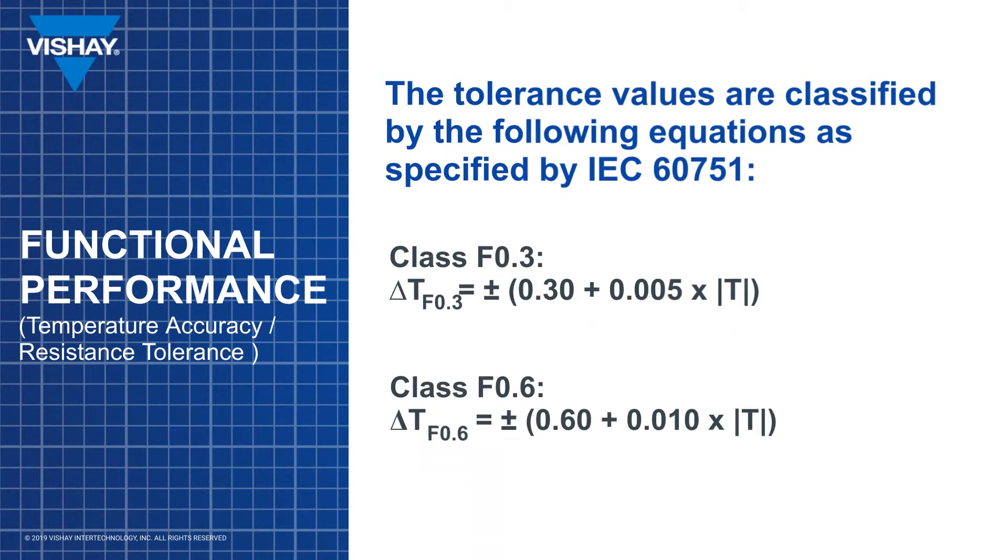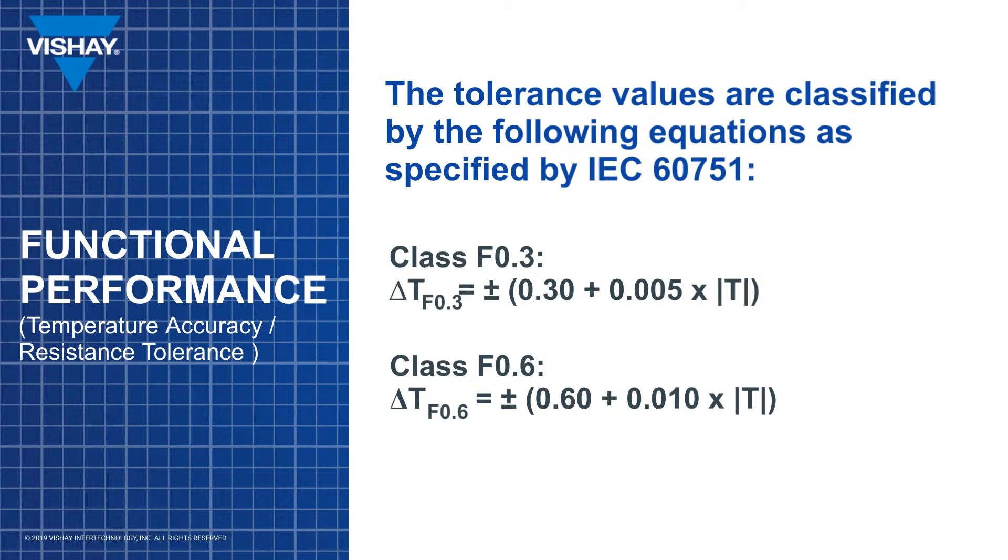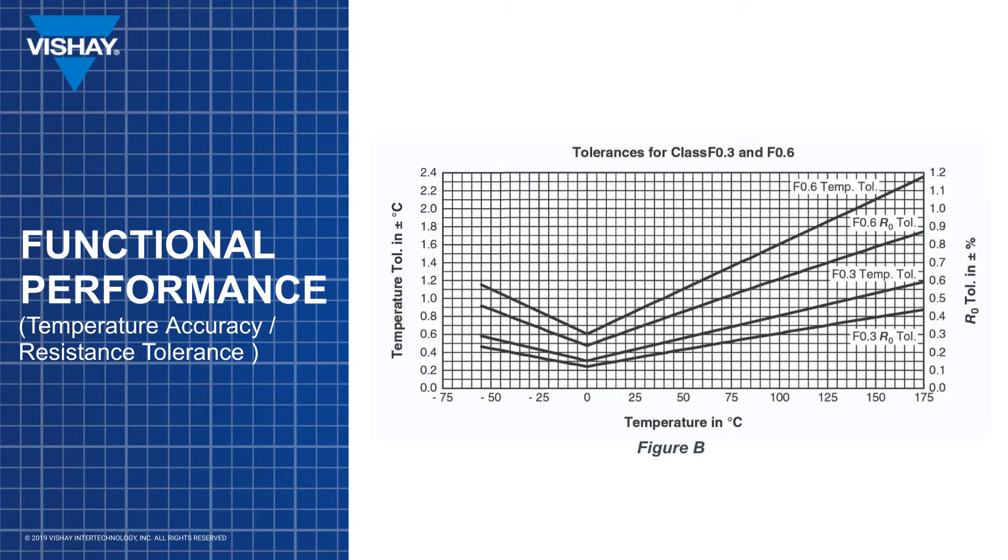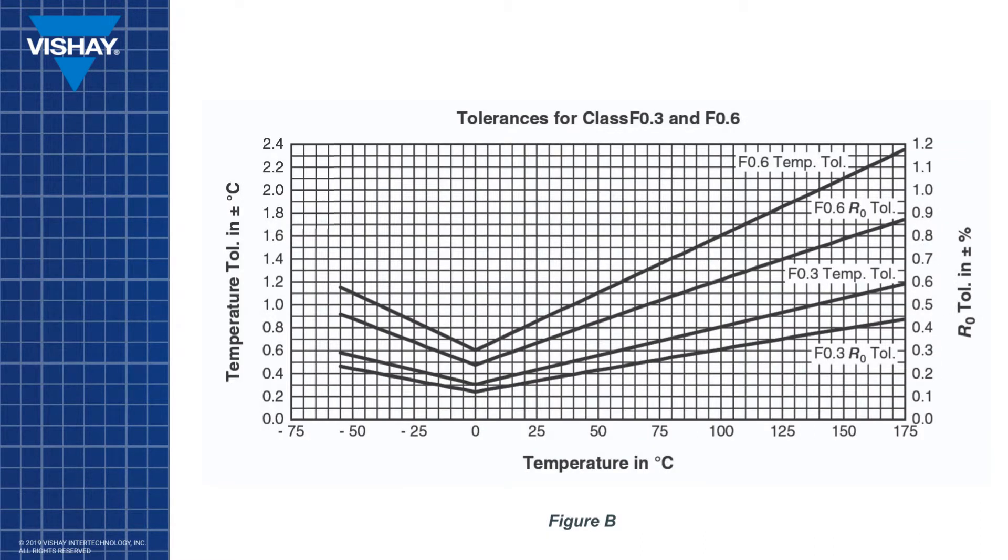The temperature accuracy and reference resistance tolerance offered by the PTS-AT is exceptional for the vast temperature range that it covers. The equations listed above are used to develop the butterfly curves outlining the temperature accuracy at a given temperature point, tolerance class dependent in figure B. As is evident in figure B, the temperature accuracy is no worse than plus or minus 2.4 degrees C for class F0.6 and plus or minus 1.2 degrees C for class F0.3 between minus 55 and plus 175 degrees C.